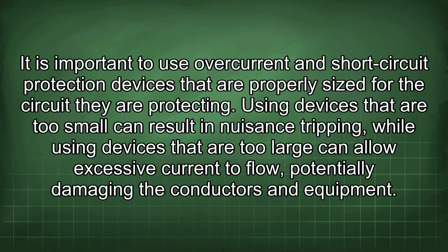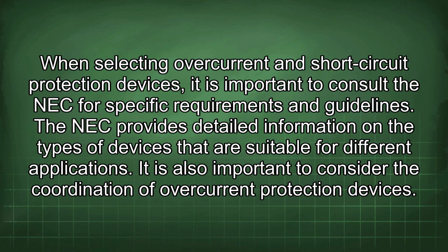It is important to use overcurrent and short-circuit protection devices that are properly sized for the circuit they are protecting. Using devices that are too small can result in nuisance tripping, while using devices that are too large can allow excessive current to flow, potentially damaging the conductors and equipment. When selecting overcurrent and short-circuit protection devices, it is important to consult the NEC for specific requirements and guidelines. The NEC provides detailed information on the types of devices that are suitable for different applications.